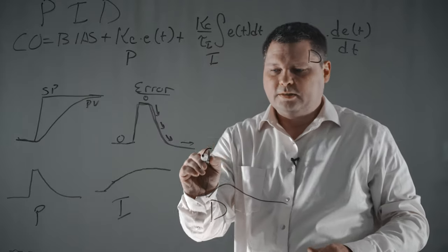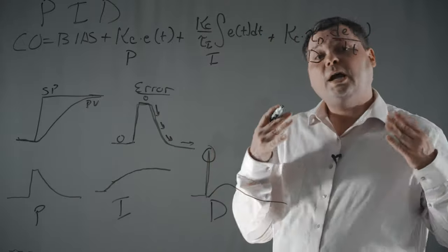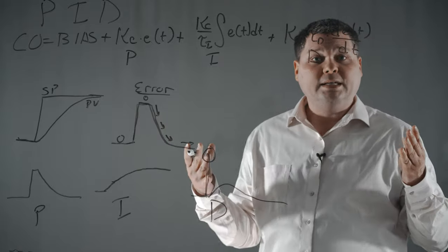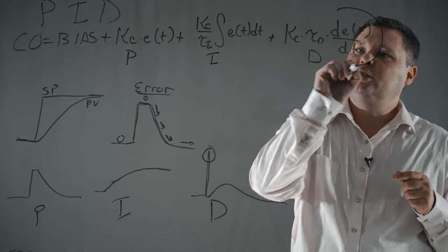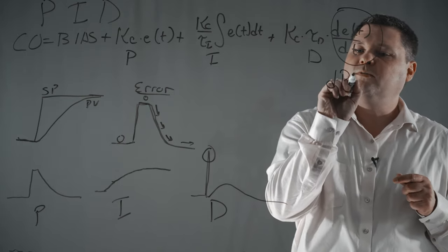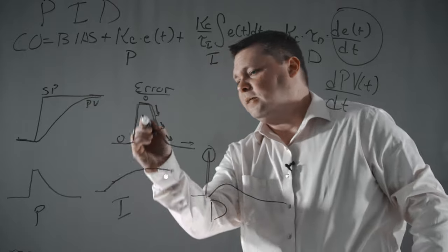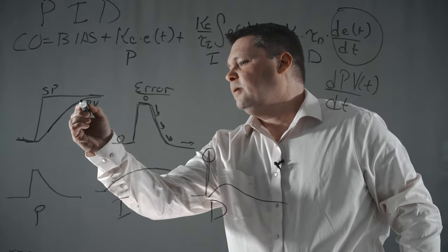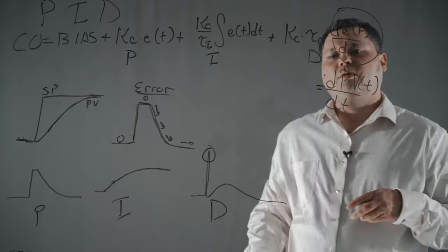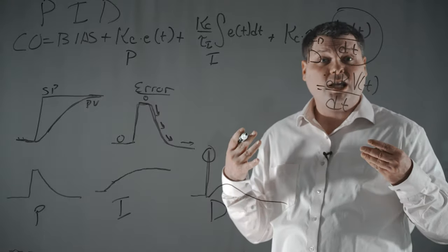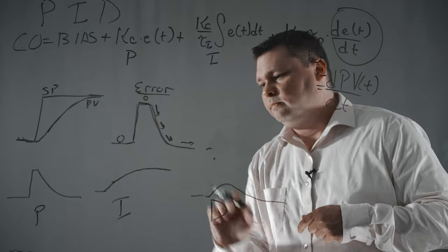This is called derivative kick, and you actually fix this in your controller by using an option called derivative on measurement. In all of your PID blocks, you have an option to switch from derivative on measurement versus derivative on error. What it does is change this term so you're looking at the rate of change of the measurement as a function of time instead of the error. Essentially, the derivative of error equals the negative derivative on measurement — so mathematically you can use them somewhat interchangeably, there's just a negative sign in front of it. And what that does is it gets rid of this derivative kick.